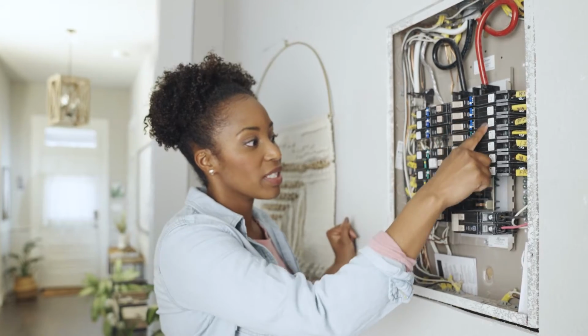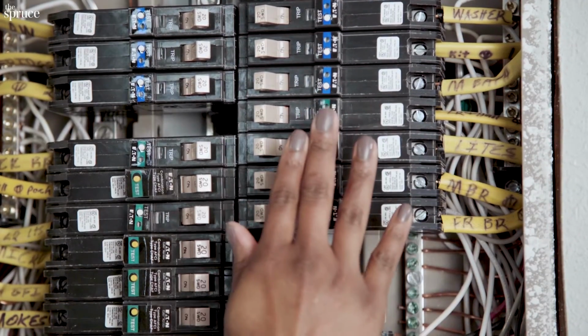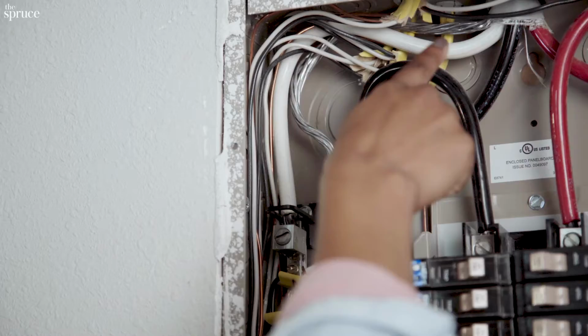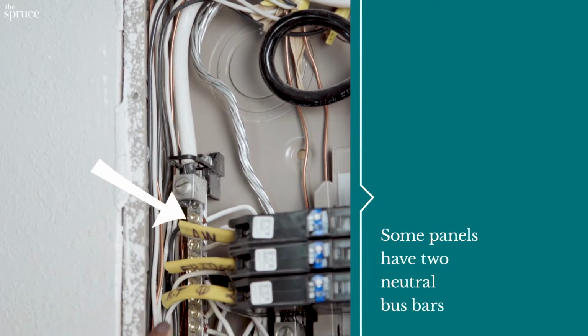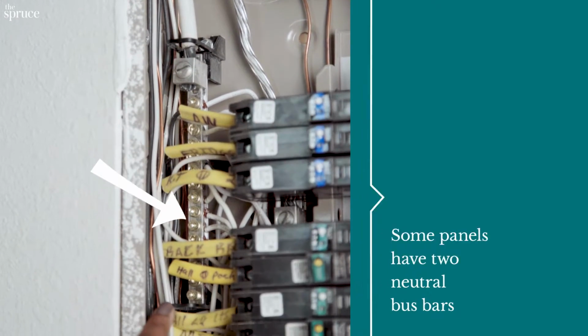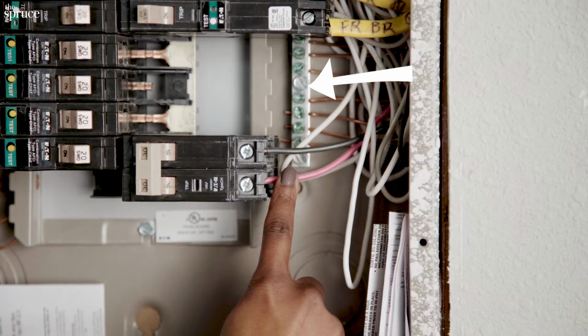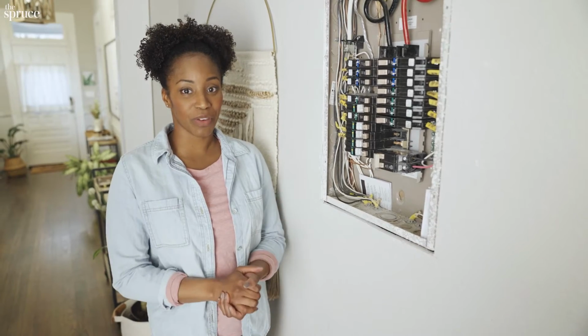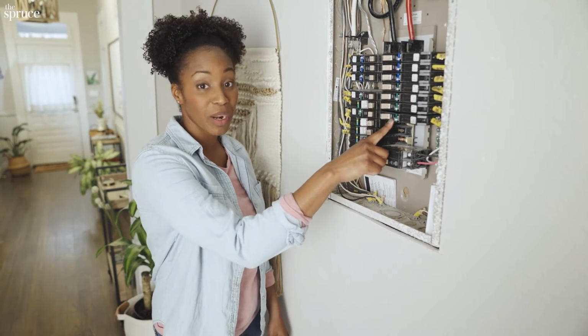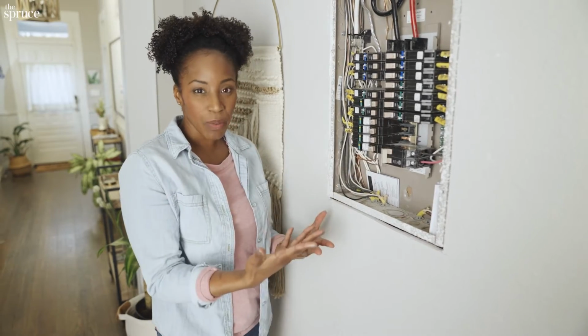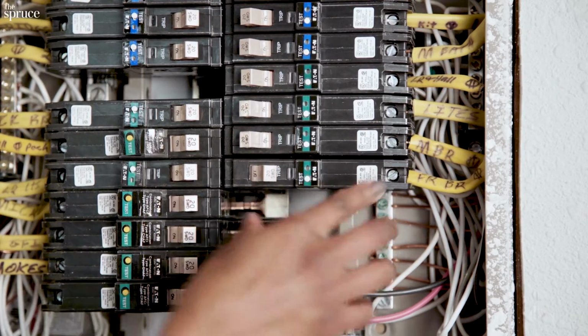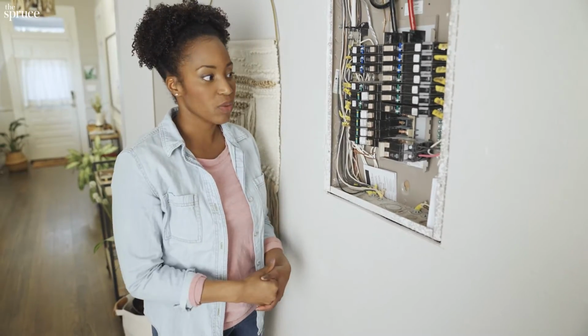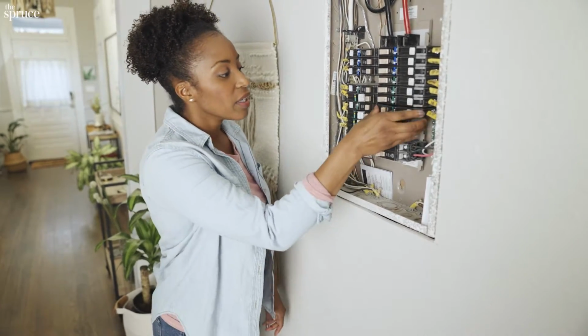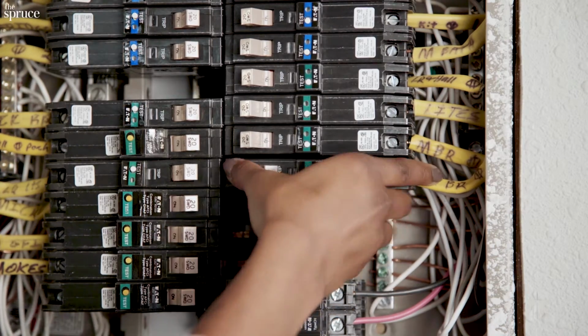And all these branch circuits snap into the hot bus bar to get power. Over here is the neutral bus bar, and right over here is the ground bus bar. Now I'm ready to remove the circuit breaker, and this is the one I'm removing. It's best practice to turn it off, even though we've already tested that no power is running. Next, you're just going to pull back on it to pop it out of place.